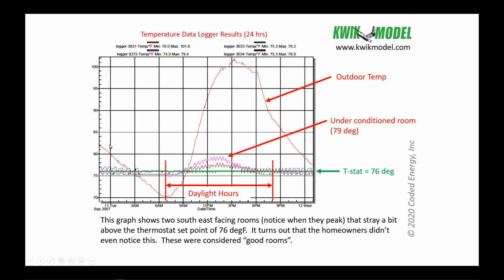So this red line here is the outdoor temperature. Now, the design temperature of this city was 99 degrees. If you look it up, it was 99 degrees. But you can see that the outdoor temperature actually exceeded the design temperature. So that's perfect monitoring conditions. That's what you want to see. That will tell you exactly whether the equipment is oversized or not.